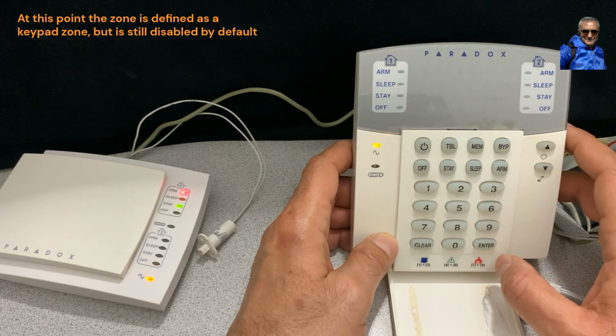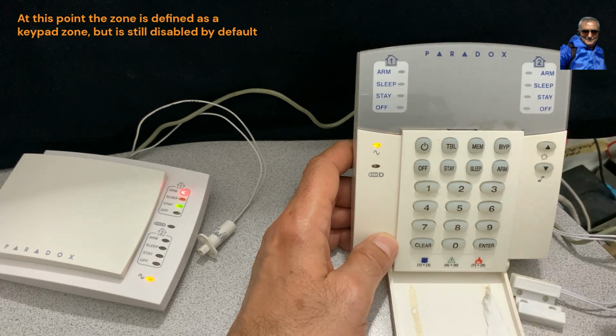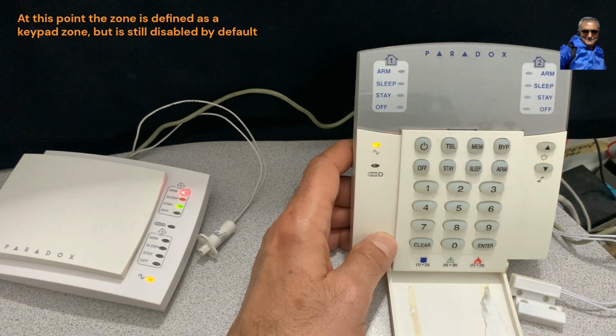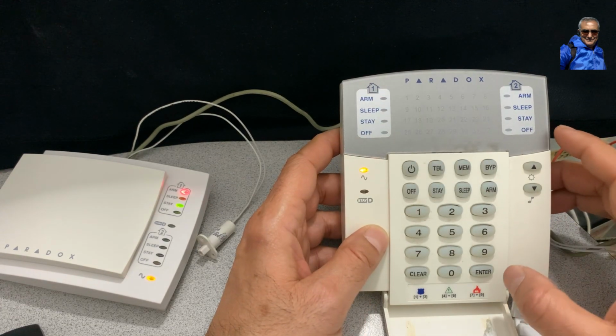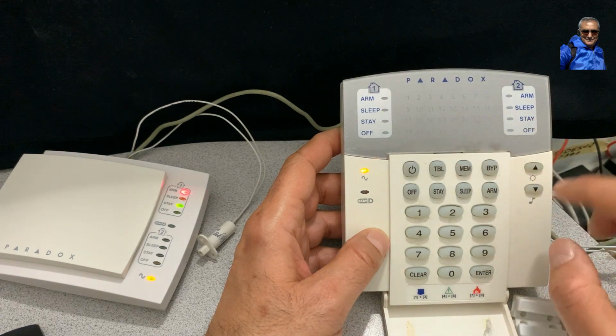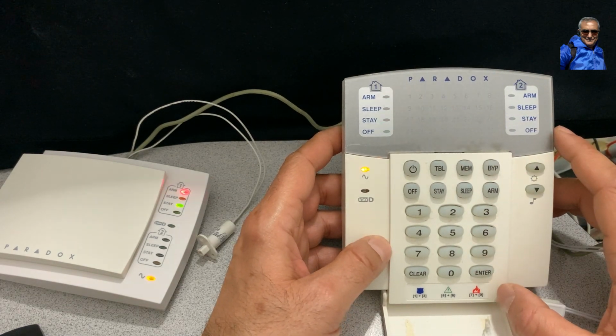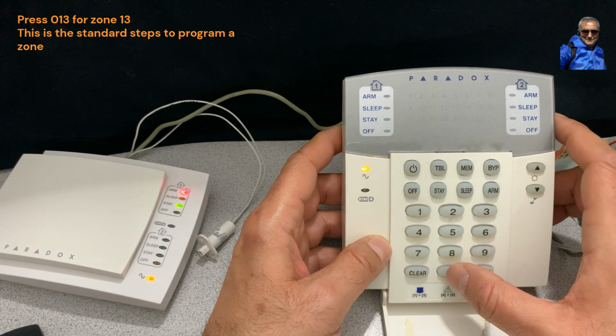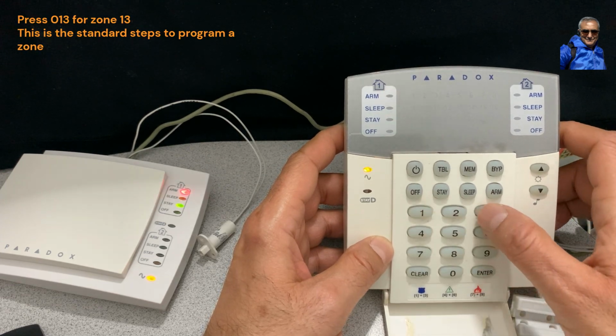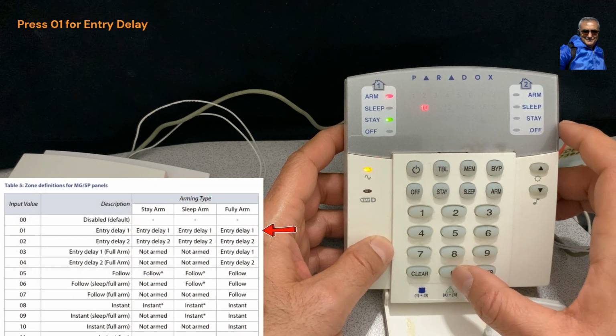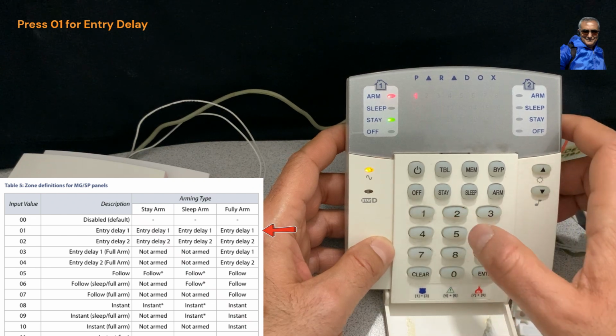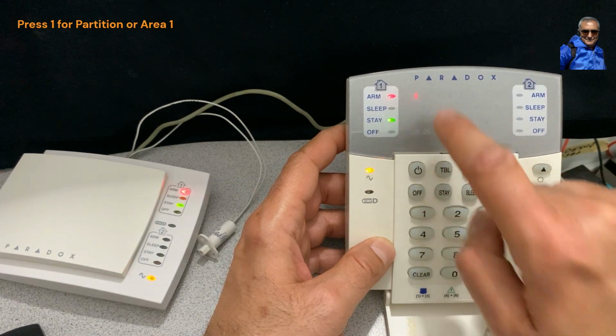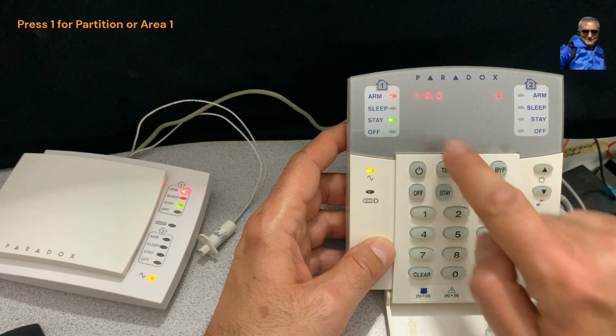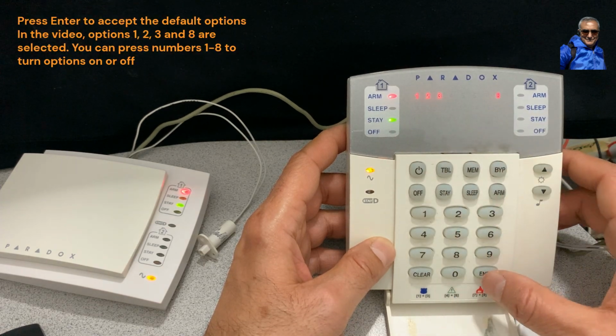At this point, Zone 13 is defined as our keypad zone on this keypad. Let's define Zone 13 to also be an entry delay zone in Partition 1. To do that, press 013 for Zone 13. Press 01 for Entry Delay Zone. Press 1 for Partition or Area 1. Press Enter to accept all default options.